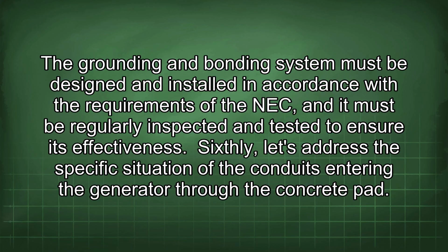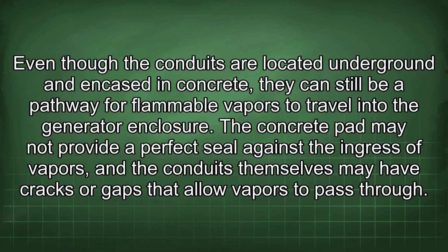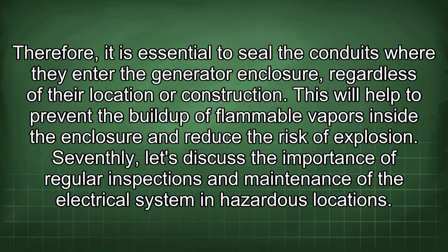Sixthly, let's address the specific situation of the conduits entering the generator through the concrete pad. Even though the conduits are located underground and encased in concrete, they can still be a pathway for flammable vapors to travel into the generator enclosure. The concrete pad may not provide a perfect seal against the ingress of vapors, and the conduits themselves may have cracks or gaps that allow vapors to pass through. Therefore, it is essential to seal the conduits where they enter the generator enclosure, regardless of their location or construction. This will help to prevent the buildup of flammable vapors inside the enclosure and reduce the risk of explosion.